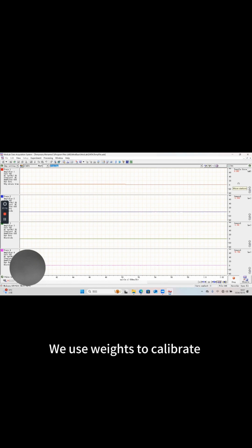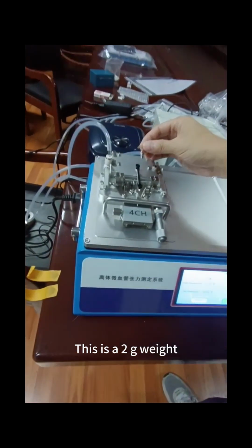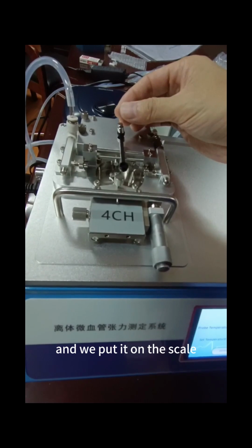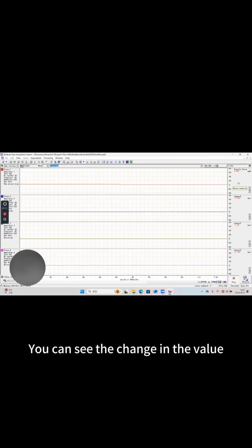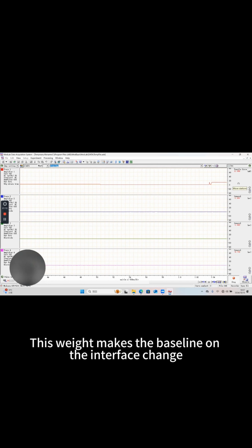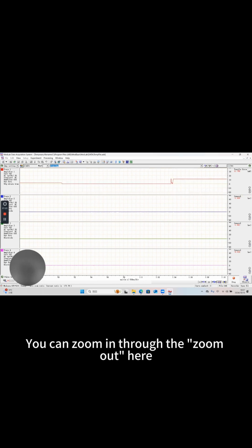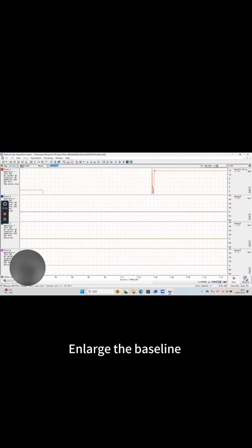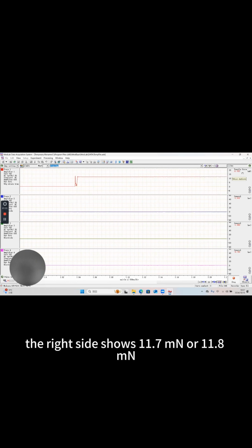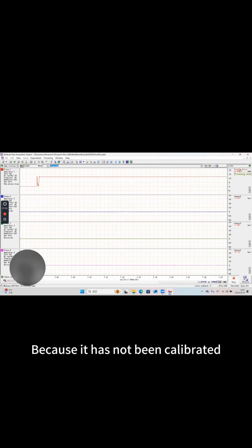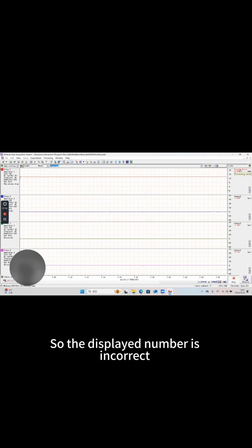Next, we use weights to calibrate. This is a 2-gram weight, and we put it on the scale. You can see the change in the value. At present, this weight makes the baseline on the interface change very little. You can zoom in through the Zoom Out here. Enlarge the baseline. Here is an example. The enlargement is a bit large. We reduce a little. At this time, the right side shows 11.7 mN or 11.8 mN, because it has not been calibrated, so the displayed number is incorrect.